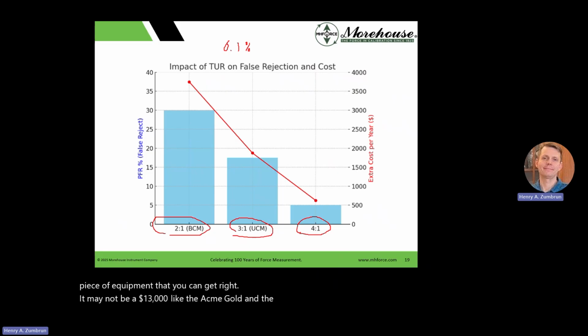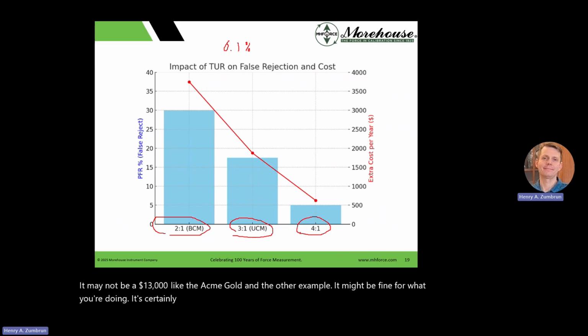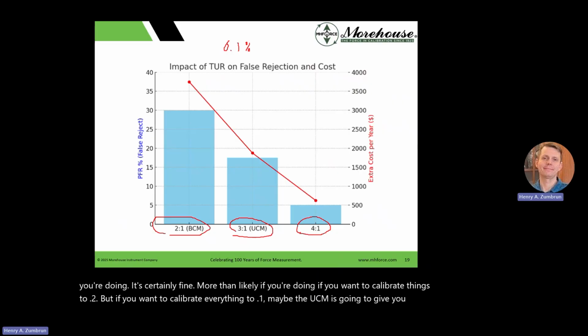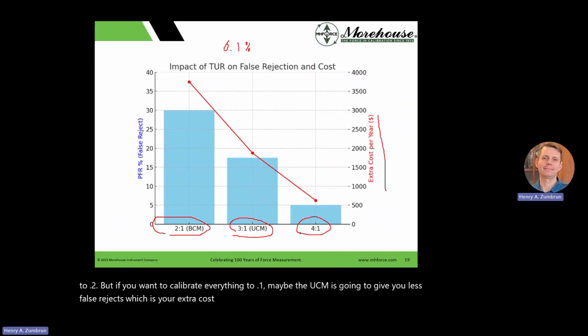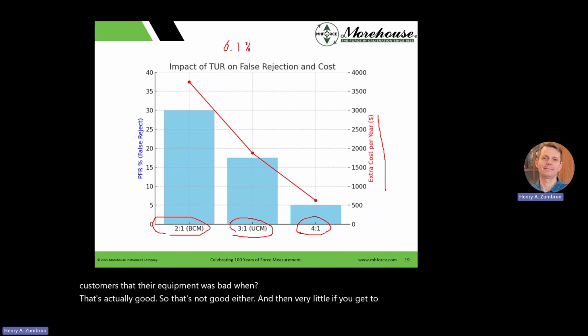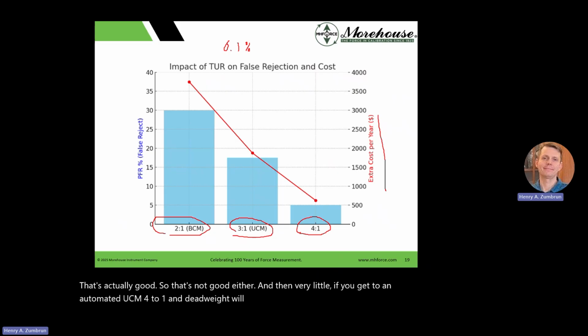It might be fine for what you're doing. It's certainly fine more than likely if you want to calibrate things to point two, but if you want to calibrate everything to point one, maybe the UCM is going to give you less false rejects, which is your extra cost per year. We haven't even talked about PFA here. This is just your internal cost. How much am I going to reject? And then I'm going to tell my customers that their equipment was bad when it was actually good. So that's not good either. And then very little if you get to an automated UCM 4-to-1, and dead weight will get you next to none.